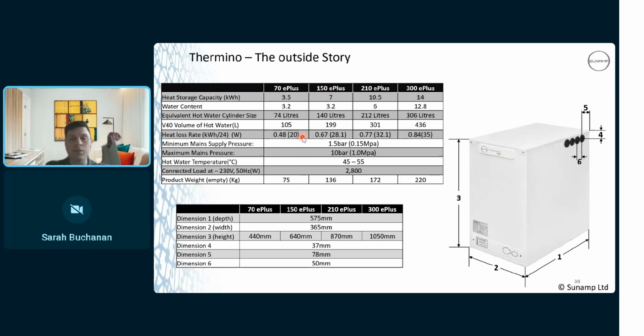So going back to your external outhouse installation, what's your ambient temperature going to be there? That's going to be much higher, isn't it? The reason I'm emphasising that is we do get some of these jobs where customers call us saying they're not getting enough hot water, and that's the reason why, because the heat losses are higher. Or on the opposite side of the coin, their energy usage is higher because their natural heat loss rate is much higher, so they're using more energy to charge it up, especially when they're not using it.